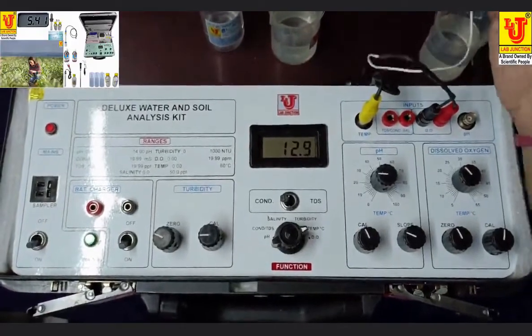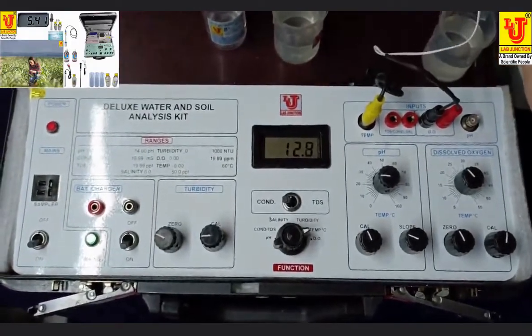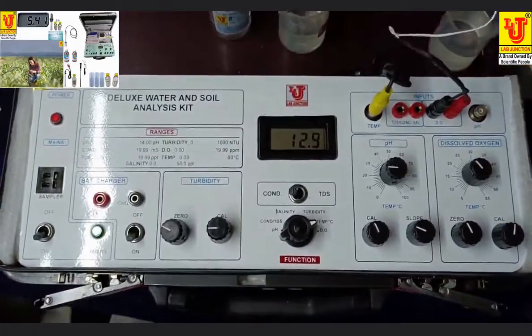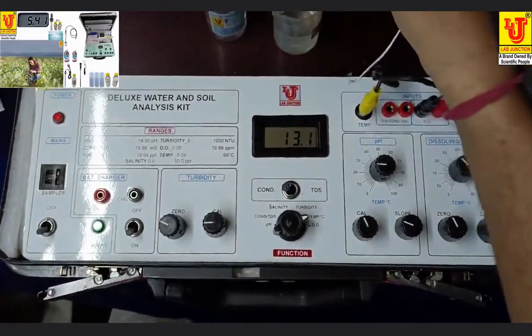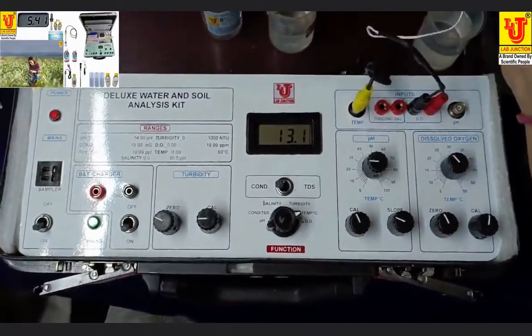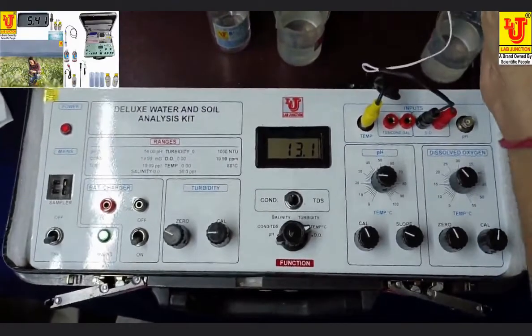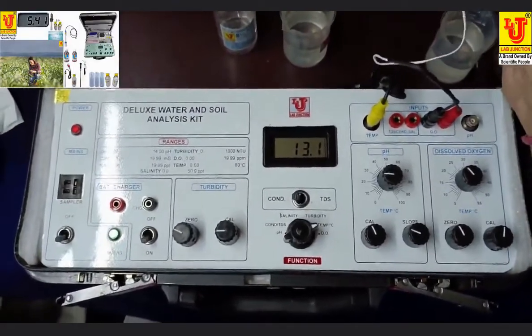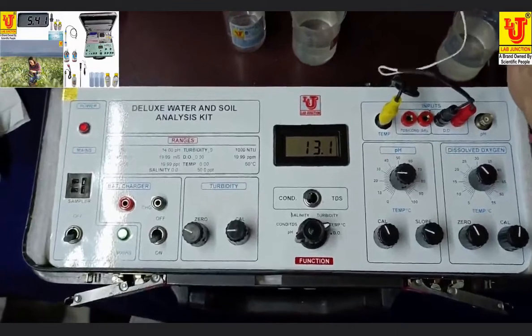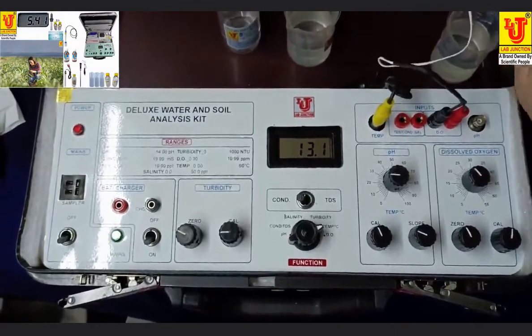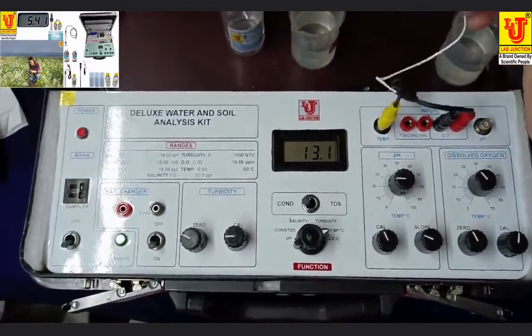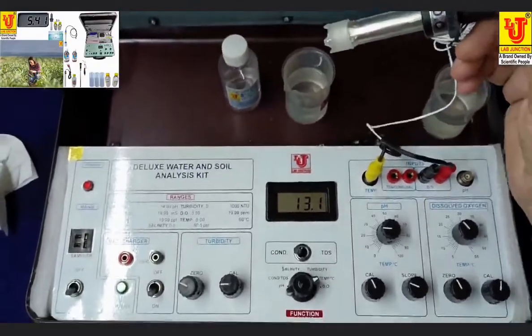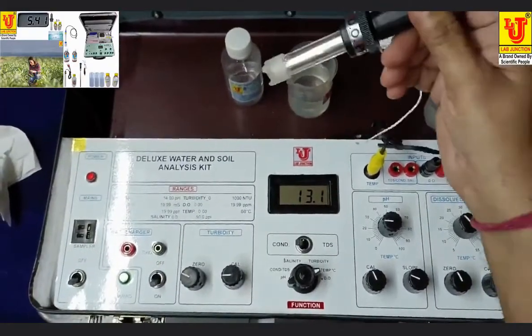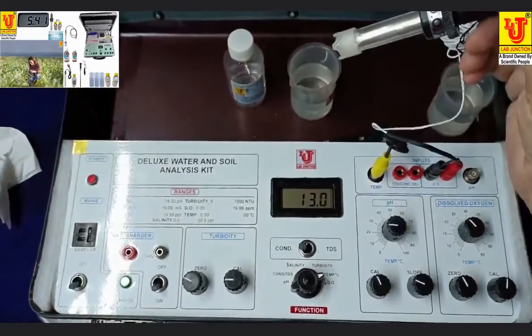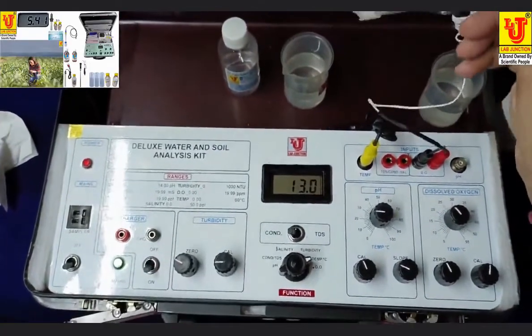Now dip your DO probe in your sample directly and check dissolved oxygen values in ppm. These are mostly used in hydroponics, aquaculture, and fishing. Now this parameter is successfully calibrated. Now your DO sensor is ready for use for taking analysis.